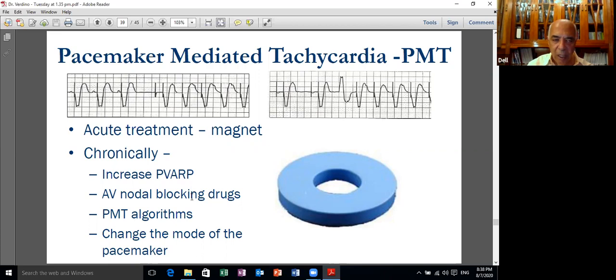the AV node, or you can use certain algorithms, like, for example, periodically increasing the post-ventricular atrial refractory period. If you get a PVC, then the pacemaker device automatically increases the P-bar for one cycle. If you get a tachycardia, then the pacemakers can interrupt the tachycardia by increasing the P-bar for one cycle and stop it. Or you can change the mode. You rarely resort to that.